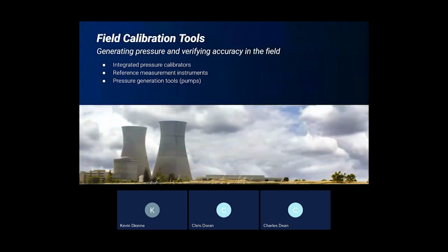Those AMETEK calibration pump systems bring everything together, but fundamentally they rely on three things: a way to generate pressure, a trusted reference instrument, and a means to verify accuracy. We're now going to look into how pressure calibrators incorporate all of those functions into one device.